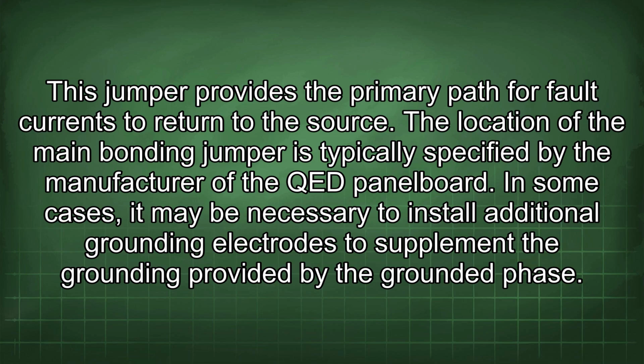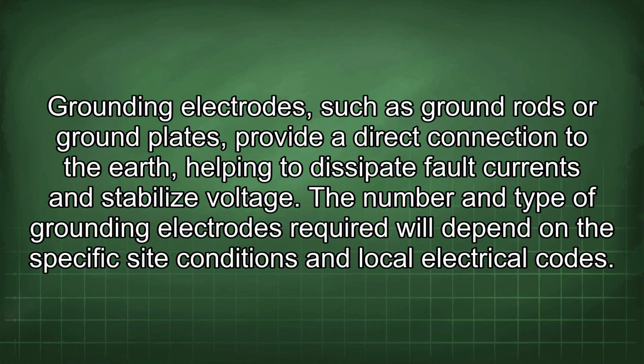In some cases, it may be necessary to install additional grounding electrodes to supplement the grounding provided by the grounded phase. Grounding electrodes, such as ground rods or ground plates, provide a direct connection to the earth, helping to dissipate fault currents and stabilize voltage. The number and type of grounding electrodes required will depend on the specific site conditions and local electrical codes.